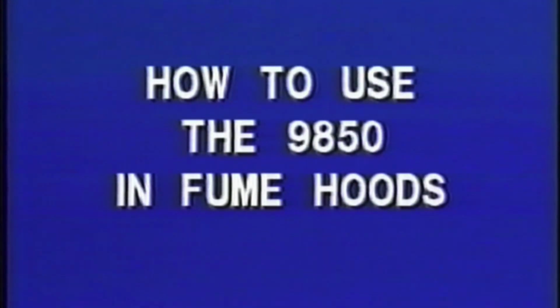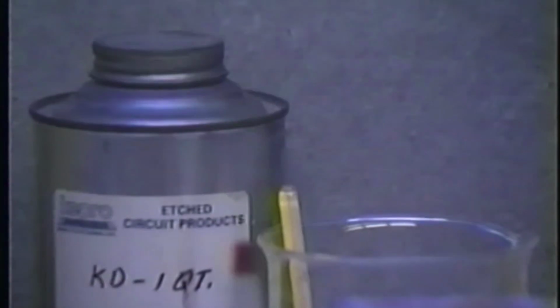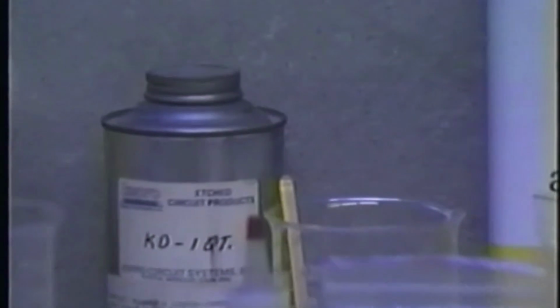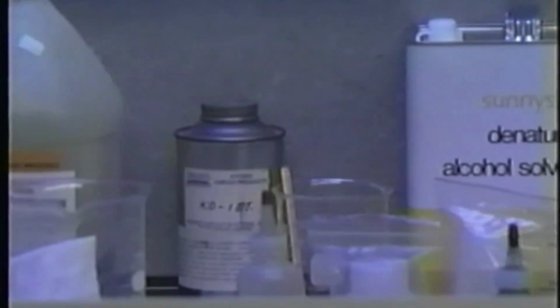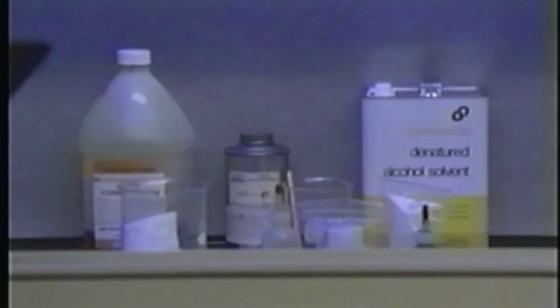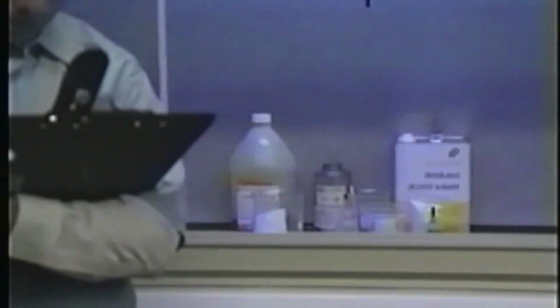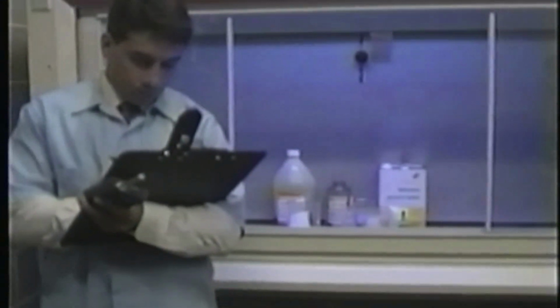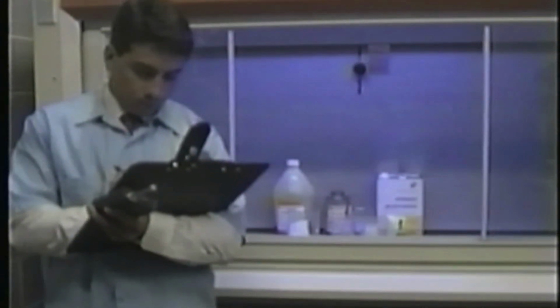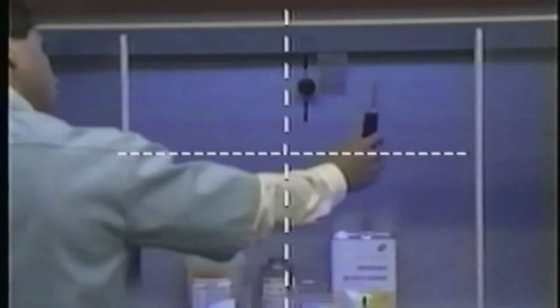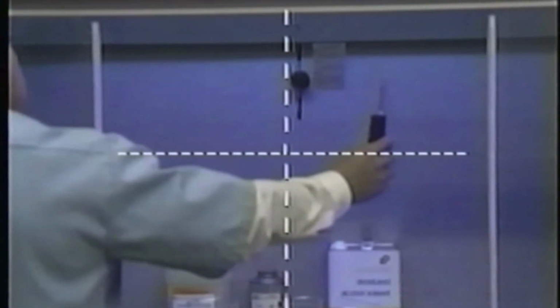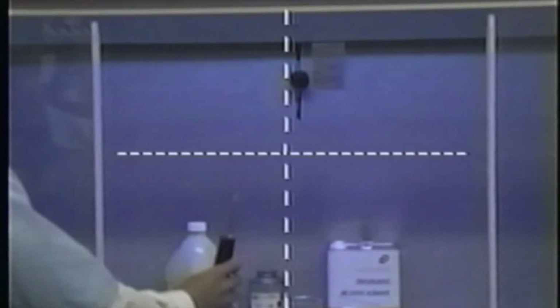Face velocities of laboratory fume hoods are established based upon the toxicity or hazard of the materials used. The face velocities can range from 50 to 150 feet per minute, depending on the fume hood class category. The face velocity shall be determined by averaging readings taken at the fume hood face. It is good practice to divide the fume hood face on a grid made up of sections of equal areas approximately 1 square foot and taking a reading at the center of each section.